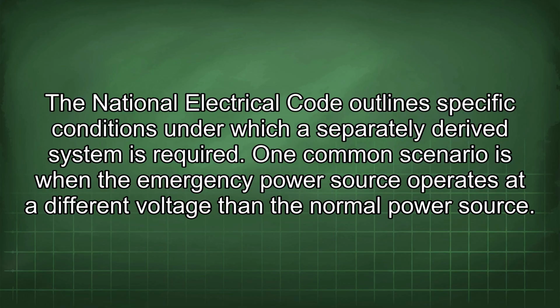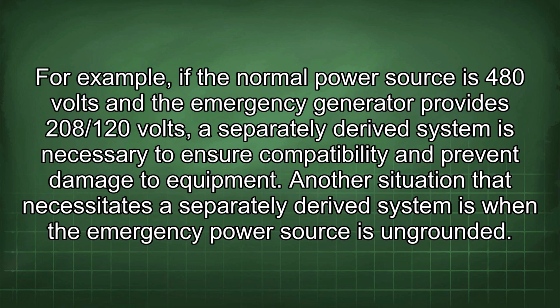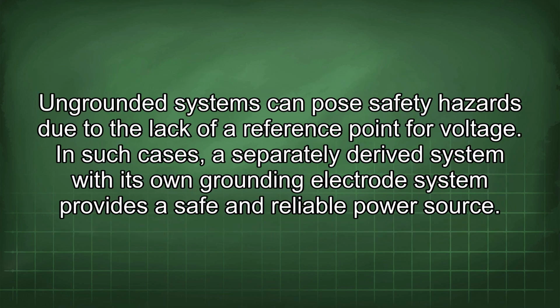One common scenario is when the emergency power source operates at a different voltage than the normal power source. For example, if the normal power source is 480 volts and the emergency generator provides 208/120 volts, a separately derived system is necessary to ensure compatibility and prevent damage to equipment. Another situation that necessitates a separately derived system is when the emergency power source is ungrounded. Ungrounded systems can pose safety hazards due to the lack of a reference point for voltage. In such cases, a separately derived system with its own grounding electrode system provides a safe and reliable power source.